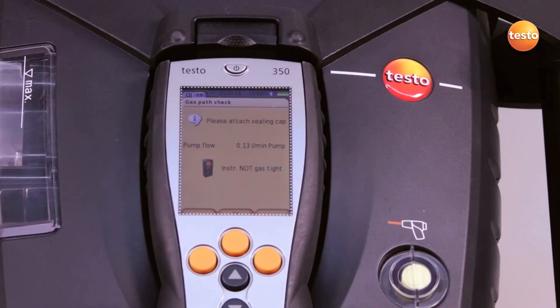When the traffic light shows green, all gas paths are tight. If the traffic light shows red, the gas paths are not tight and must be tested for leaks.